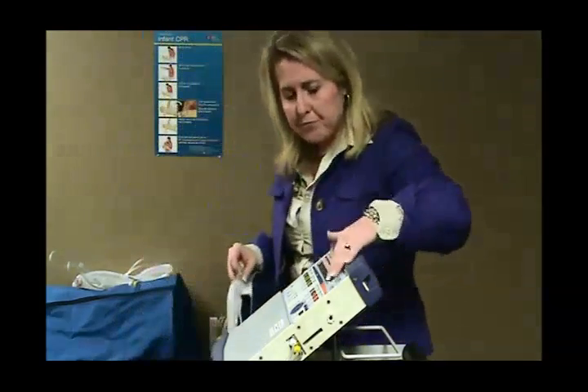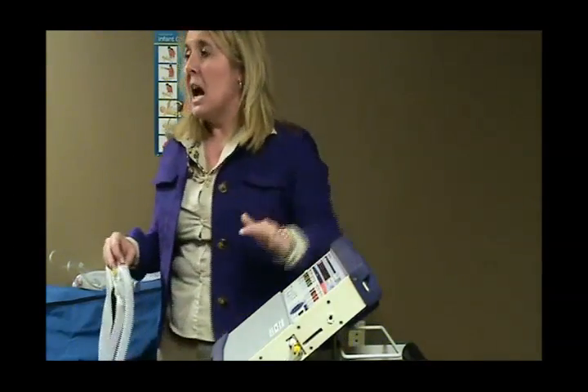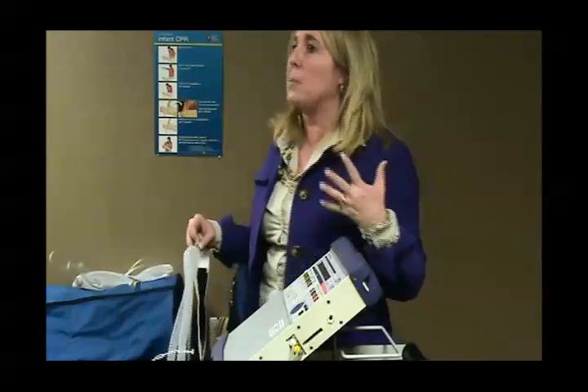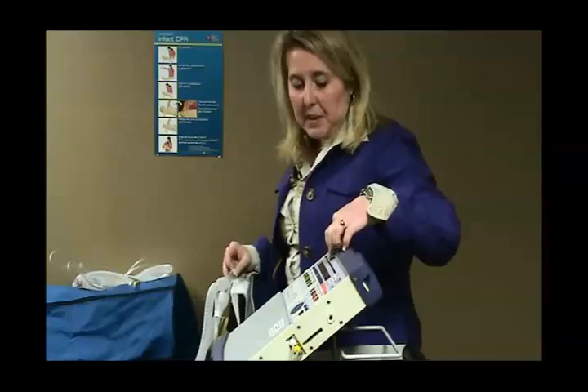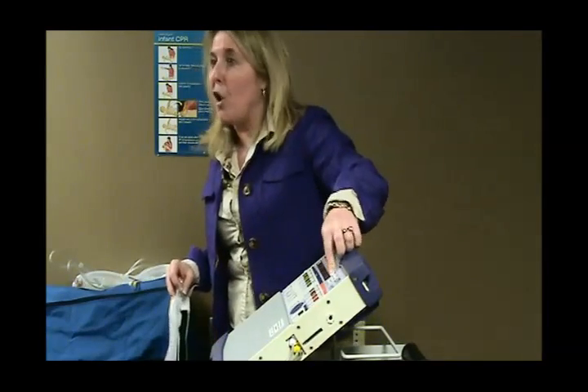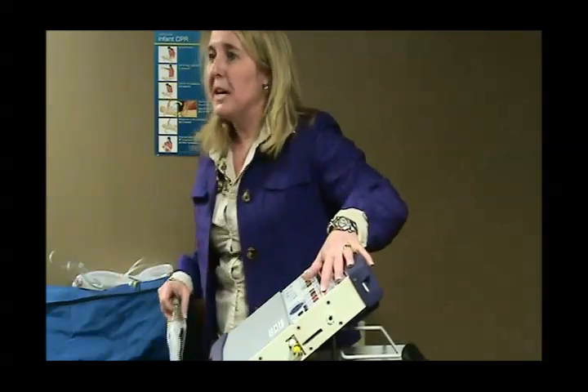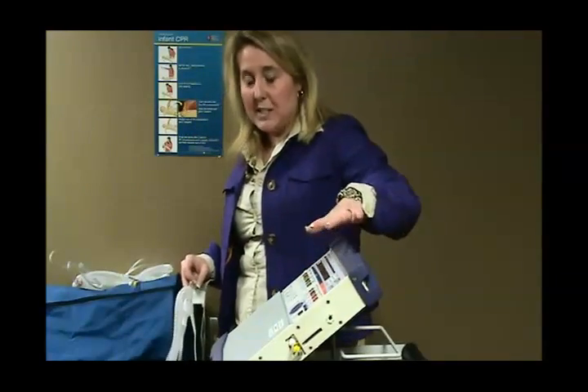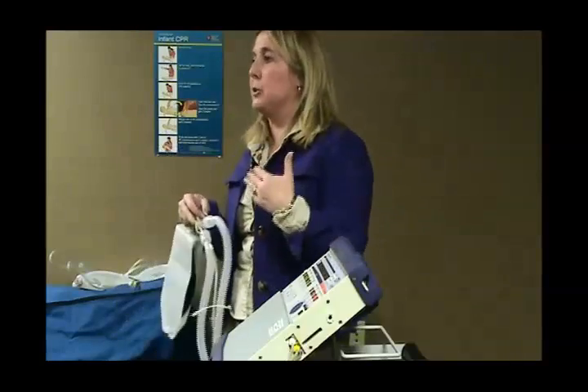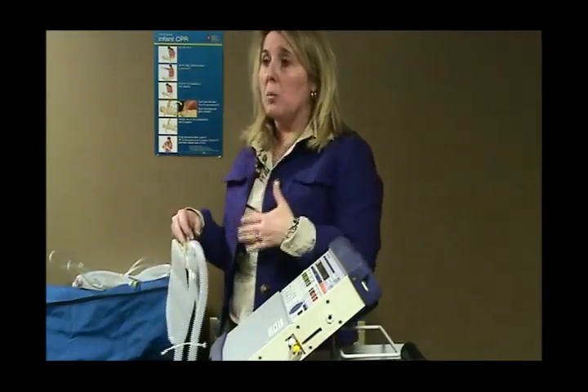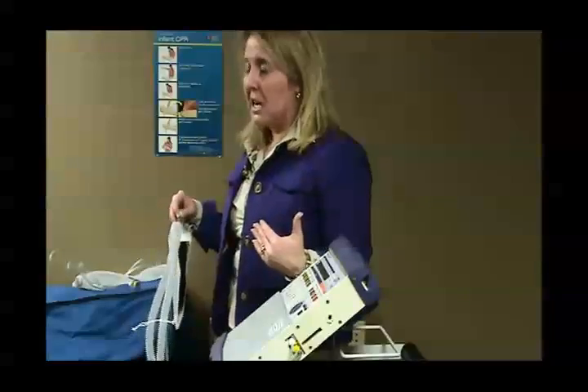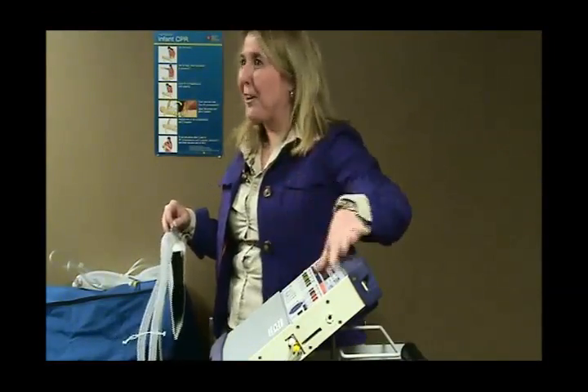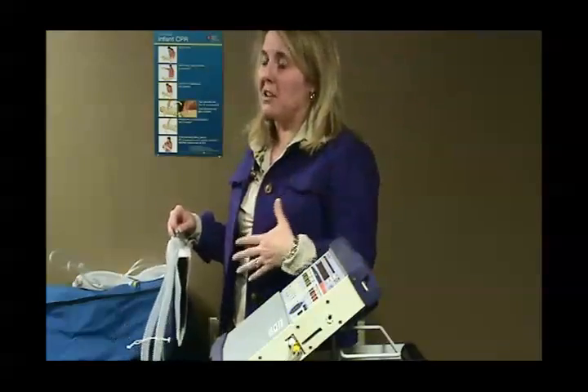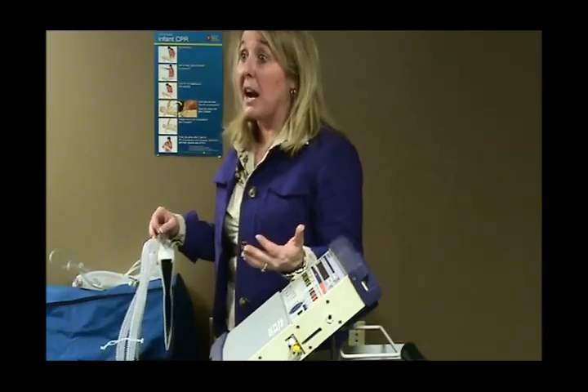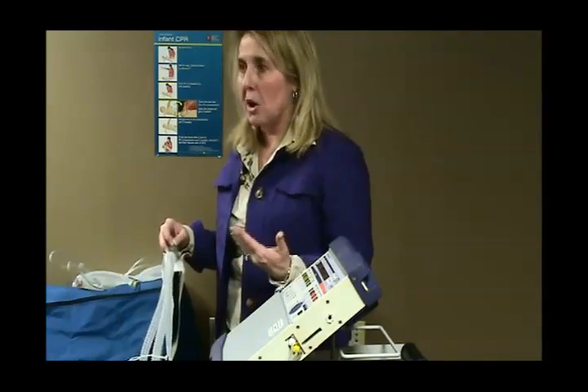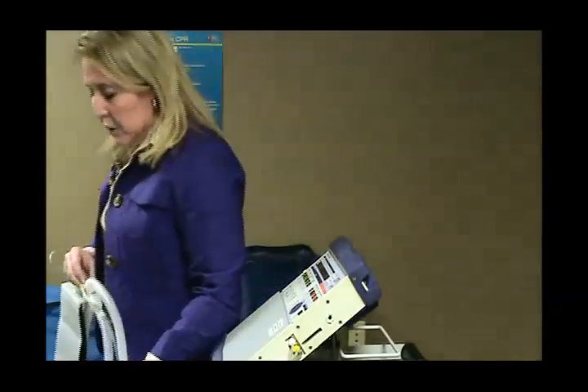Other alarm messages. If you have other alarm messages that pop up in here, they should be pretty self-explanatory, high pressure, low pressure. Once in a while you'll get something. This one I created just so that you could see it. High F off. The ventilator is not cursing at you. It means that there is a high respiratory rate alarm that is set in the back menus by the RTs at the hospital before the patient goes home. If somebody turns that to the off position, then on occasion it'll pop up high F off. It's just to remind the caregivers that you don't have a high respiratory rate alarm set. And that's fine. That's one of those alarms that the RTs have discretion on, turn on or off for different reasons. So that's all the other alarms.